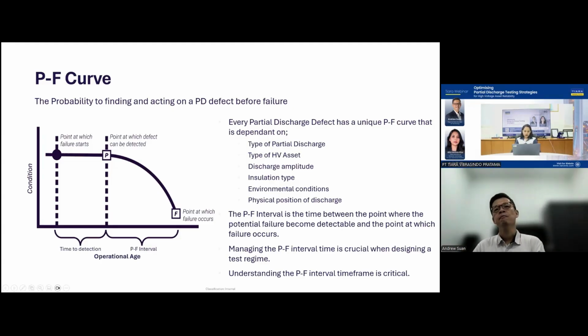It can be internal discharge, it can be surface discharge. And if it's corona discharge, then it's good, because if it's discharging to the air, we do not have a concern. But if it's pointing to my bus bar, then maybe there will be a problem. Okay, so the first thing you determine is what type of PD it is.